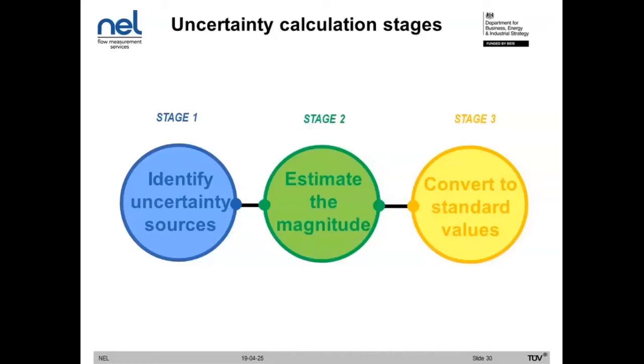The next step, once you have your various types of uncertainty sources, is to estimate the magnitude of them, and the difficulty of this process depends greatly on the information you have available and the type of the uncertainty source. Generally speaking, a resolution uncertainty is very easy to quantify, and you can do it very accurately without too much difficulty. There are other uncertainty sources that aren't so easy to quantify, so you could have something like the effect of electromagnetic noise, for example. This is something you'll just have to make a good estimate for and try to be conservative. When in doubt, you basically try to assume the largest value possible that is realistic. You try to be pessimistic rather than optimistic in this case. The key is to be conservative.